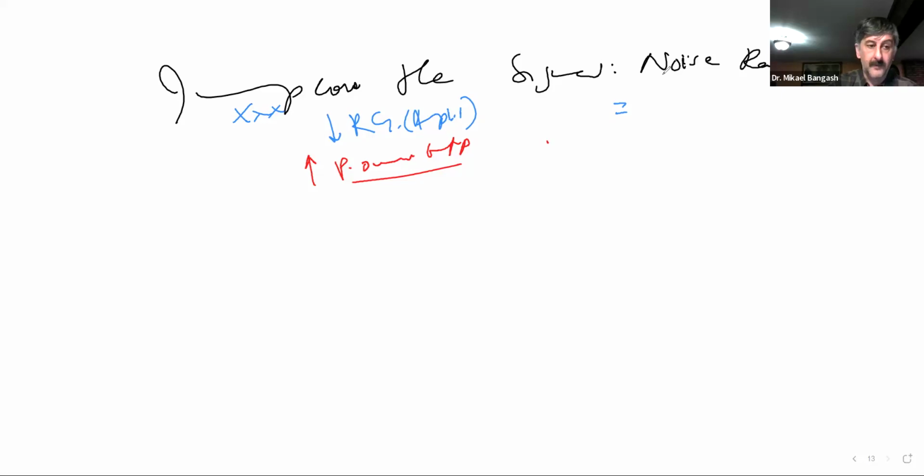So what we actually said was, a way of improving your signal to noise ratio is to produce more signal and less noise, which was to increase the power output, or transducer output, or output gain, energy output, pulsar power, acoustic power, transmitter power.